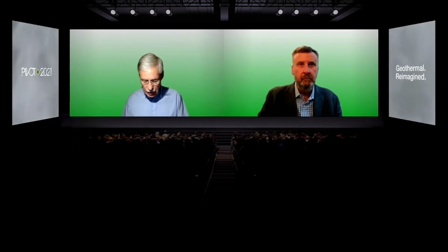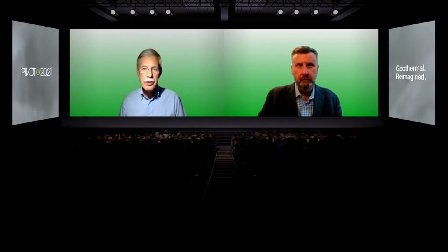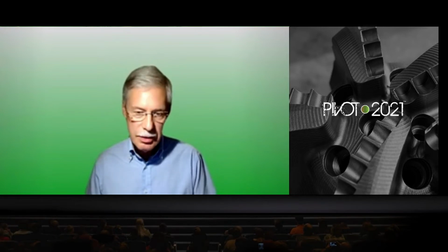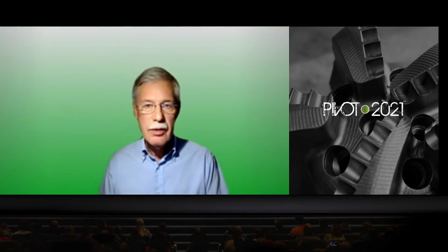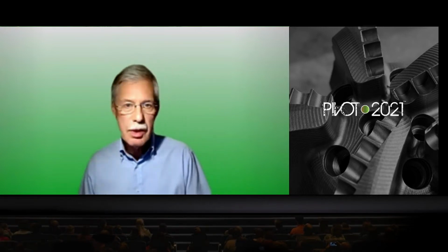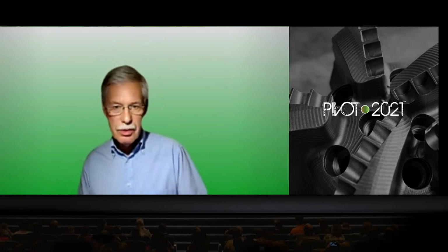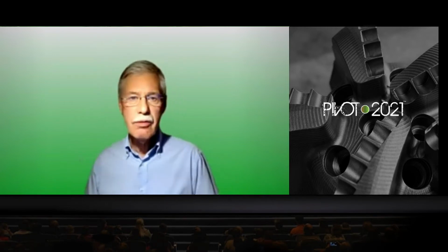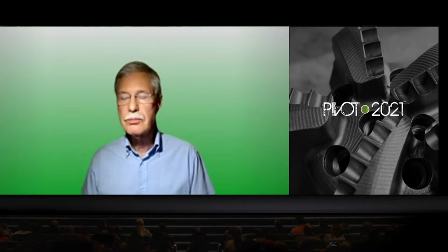And as well, we need, especially in the Rheingraben, the line shaft pumps Patrick already mentioned. Due to the fairly high brine temperatures, we cannot operate ESPs there. So we have to install line shaft pumps, which is a technology which is now very reliable, and we are very happy to operate those now.